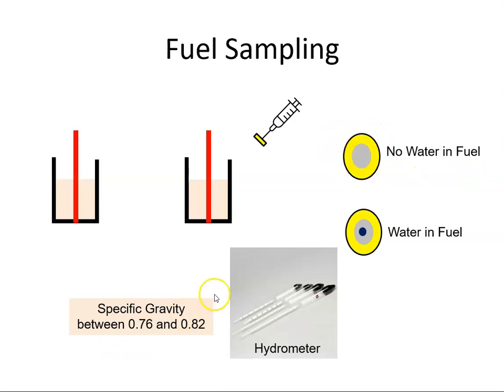Another alternative is to use a hydrometer, which measures the specific gravity of the fuel. For Jet A1, the specific gravity should be between 0.76 and 0.82. As long as the fuel is within those ranges, it would be acceptable.